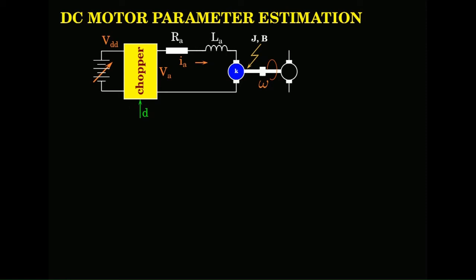Then on the mechanical side we need B, right. K alone you need to change the setup because you are not doing it on the same machine. So, RA, LA, B and J are on the same machine, so self commissioning you can do further. K alone you will have to change, you do it once and then keep it aside, you can feed it as a parameter.